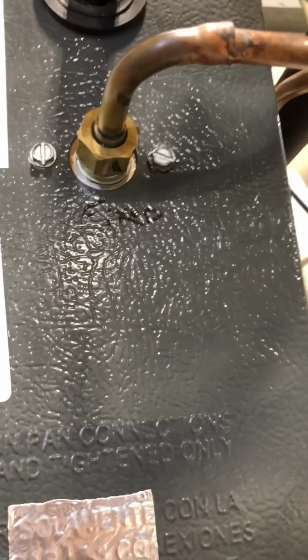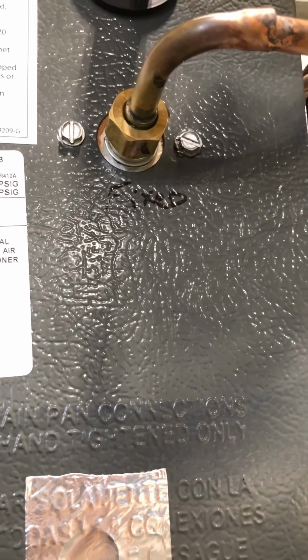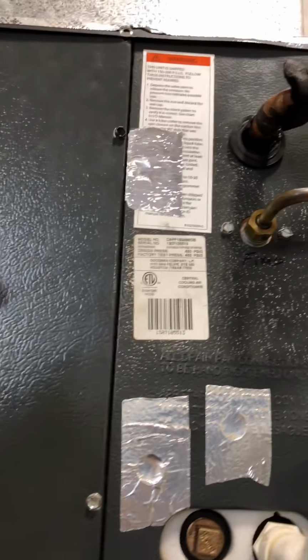We also have to know what type of metering device we have. Okay, right now this is a fixed orifice. I have it written there. Most fixed orifices are going to have a big nut on the outside like that, but visually check. You're going to go in here. You've got to check this coil anyway to make sure it's clean, to eliminate that there's any problems there. So just look inside.